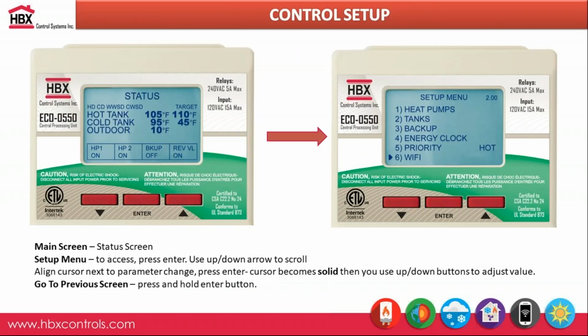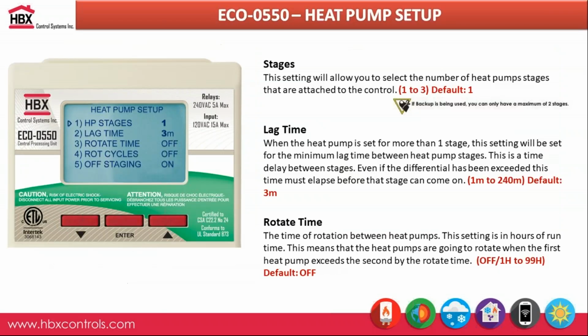In terms of navigating the controller, it's very straightforward. It's just up and down and enter. If you hold the enter button down for 2 seconds, it takes you into our setup menu. So here you're able to navigate your heat pump stages, tank temperature options, backup options. If you want to use it as an energy clock, you can do that as well, and give the controller priority, and hook the controller up to a Wi-Fi network on there.